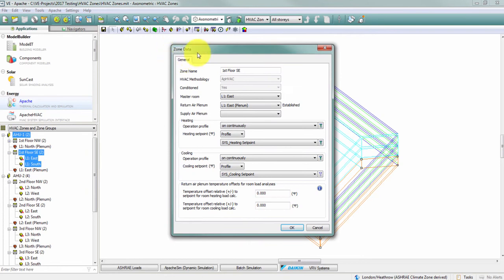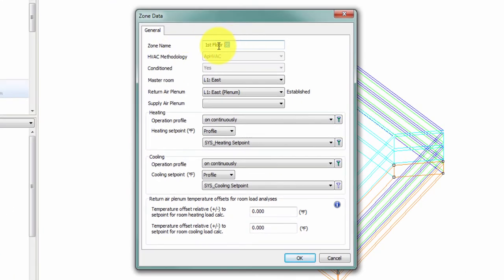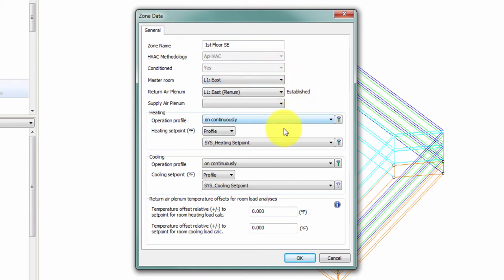Here I have the name of the zone that I have the ability to edit. I have the master room that I can change with the pull down menu as opposed to the right click set master room option. I have the return air plenum, and I can see the heating and cooling set point assigned to this zone. If I want to change the temperature offset associated with the return air plenum, I can do that in this dialog as well.